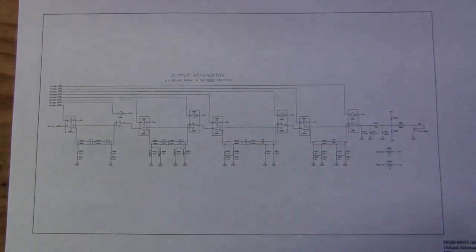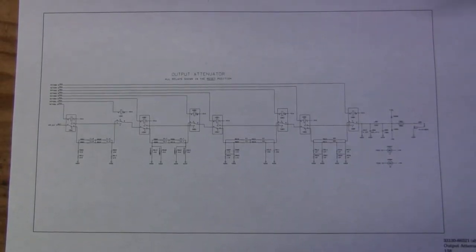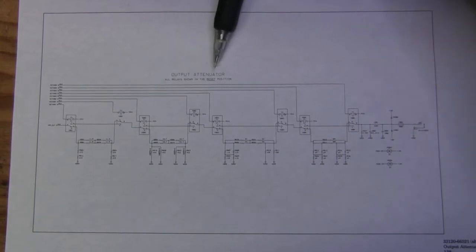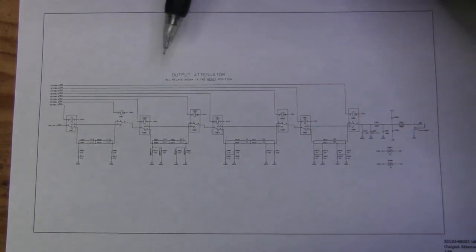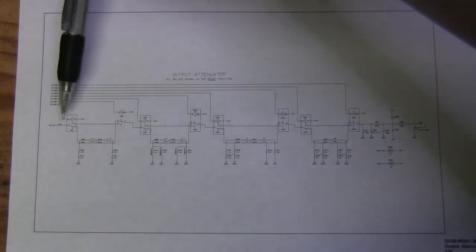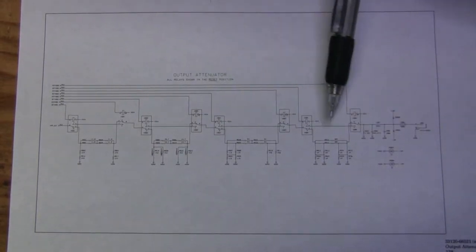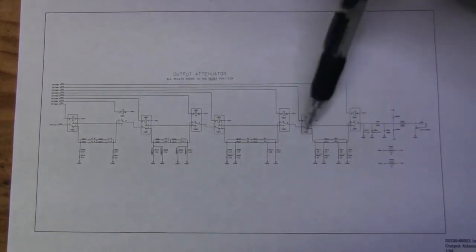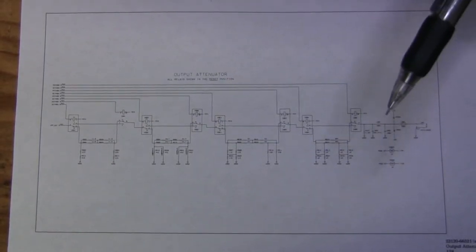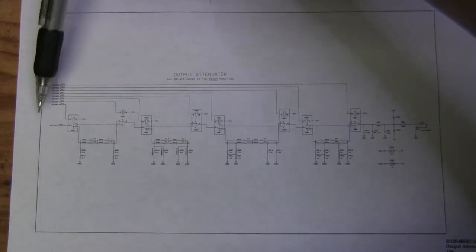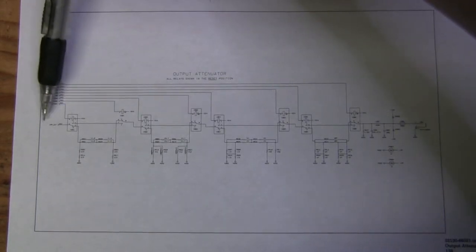So in the previous video we briefly looked at this output attenuator circuit. If we look a little closer, we can see these are relays which are clicking and these are dividers for different ranges.